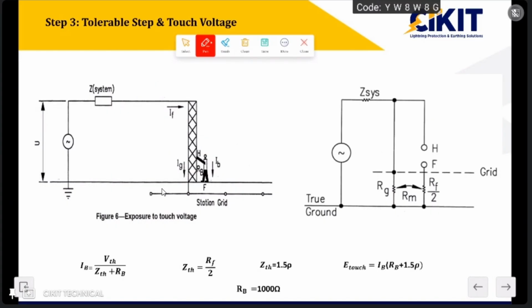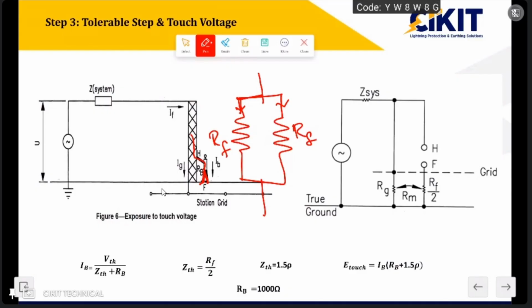So here what is happening? The fault current is flowing through the body and it will be discharged through the foot resistance. There are two options. The current can discharge from one foot to another foot. RF is nothing but the foot resistance. Since we have two feet, the discharge takes place through two parallel paths, and if the resistance is the same, the effective resistance will be RF by 2. So in this case, Z Thevenin will be equal to RF by 2, and if I substitute this value, I can get the touch voltage.